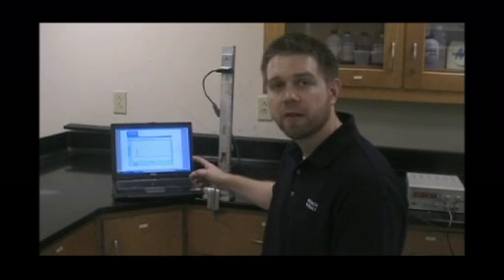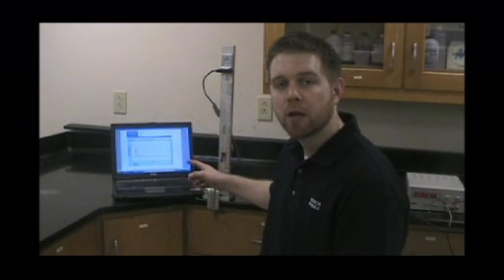The 0 to 5 volt output of the sensor is being monitored on this computer so we can watch the response of the sensor as the hydrogen goes past.